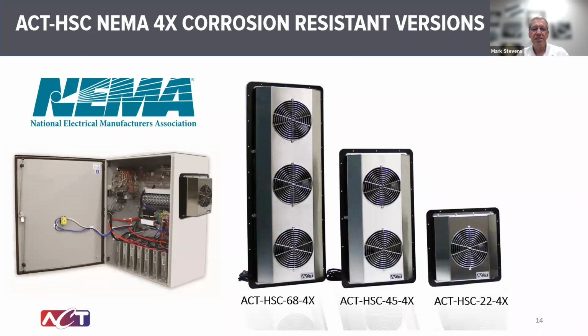One of the nice things is that if you have a very caustic environment where there's acids, salt sprays, wash down or spray down chemicals, like in food processing, we have a NEMA 4X line, and they're all stainless steel. The fans are potted, so whatever's happening on the outside of the cabinet isn't getting into the interior. If you see around the rims of those products, there's a black center plate, coated with something called electrofin coating. The cooling fins on the sides are also coated, and that electrofin coating gives you security against corrosive atmospheric environments or chemical sprays.